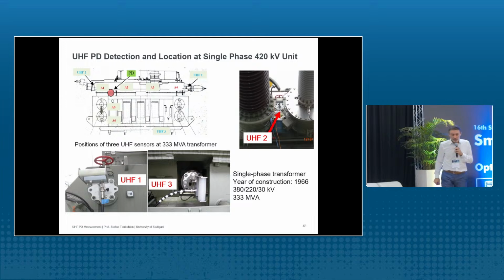Second example is a 400 kV unit, a 50-year-old transformer, and with this transformer the operator detected hydrogen, which is a sign of partial discharges. Then he decided to do an electrical PD measurement. This was not possible because above the transformer there was the bus bar, and there was some, of course, PD on the bus bar in air, and these PD were so strong that you could not measure any electrical PD inside the transformer.